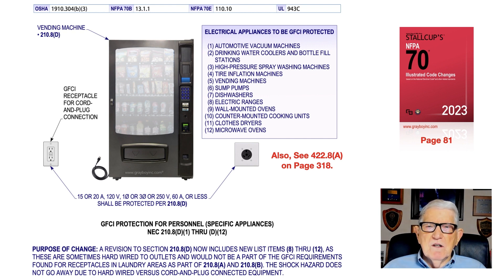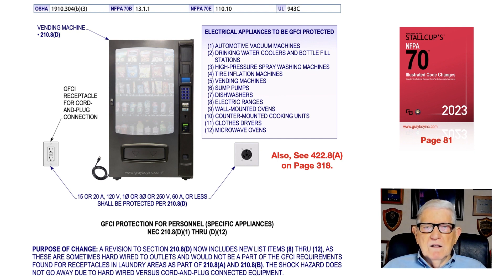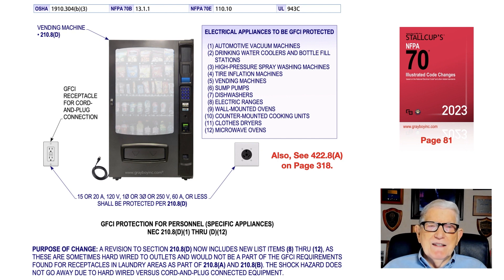This illustration shows a vending machine with a GFCI receptacle for cord and plug connected equipment. If it's not a receptacle, then a circuit breaker with the GFCI protection scheme would be used. This section deals with GFCI protection for personnel for specific appliances in accordance with 210.8 D1 through D12 — that is 210.8 D on page 81, which is the purpose of this change in the 2023 edition of the NEC.